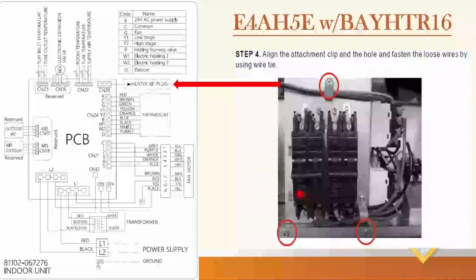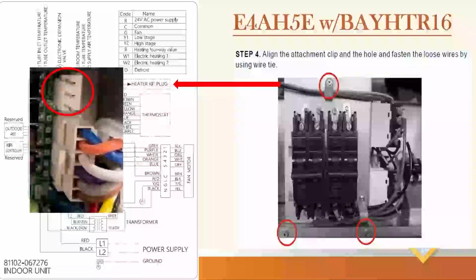As you can see right here, that's a 60 amp breaker, but this could actually be rated for 35 amps. So keep that in mind. This is not a circuit breaker. It is a disconnecting means. It's just a light switch, just going to allow you to switch that off at the unit. And there's a good close-up picture of that CN20.